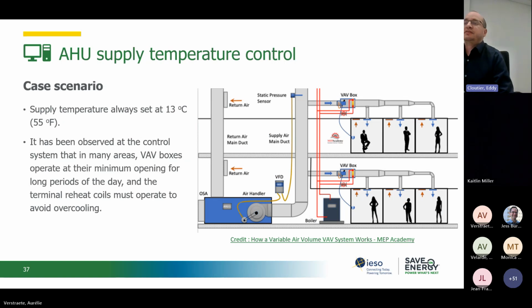A similar measure on a ventilation system. Here you have on the right the schematic representation of a typical variable flow ventilation system with terminal reheat. Basically, each VAV box will reduce its flow to a minimum, and if necessary, of course, the terminal reheat will start working to make sure that the supply temperature does not produce overcooling in the rooms. In that case, the operator was always operating the system at a fixed supply temperature set point of 55 degrees Fahrenheit or 13 degrees Celsius. What it caused was that there was a lot of partial occupancy of this building, so a lot of reheat was needed at all times, even during the summer.